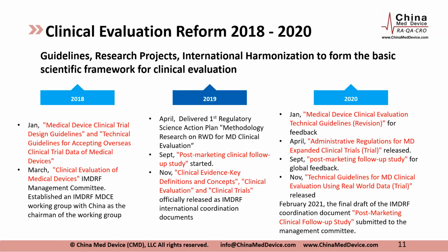As NMPA is learning, you can see that in January 2018 China developed more detailed guidance, whether clinical design guidance, and then it allowed overseas clinical trial data. Before this clinical trial data acceptance was released, it didn't matter whether you did an overseas clinical trial, you still had to repeat it in China. So in the past few years, overseas acceptance for IVD has a different acceptance guidance. So medical devices and IVDs both have NMPA-published acceptance guidance.